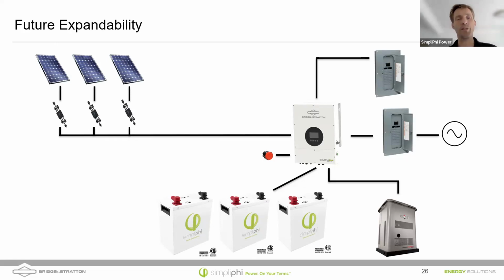So this is a DC coupled system. What you can see are rapid shutdown modules that I'll be putting on my SunPower solar panels, with a rapid shutdown button at the inverter. The SimpliPhi battery bank, just 3 batteries, gives me about 12 kilowatt hours of storage. Since I'm only using about 10 kilowatt hours of battery energy over a full day, it should be enough for me. I'm going to use a critical loads panel to back up things in my house that I want to stay on, and maybe in the future I'll add a generator if it proves necessary.